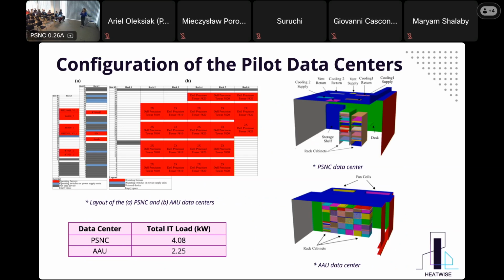Depending on the data center's layout, you can construct your model at either the server level or the rack level. If you have empty servers in a rack, it may be more sensible to use server-level modeling. But if you have many servers in your rack, you'll use rack-level modeling to identify cooling capacities and other model inputs for better accuracy.